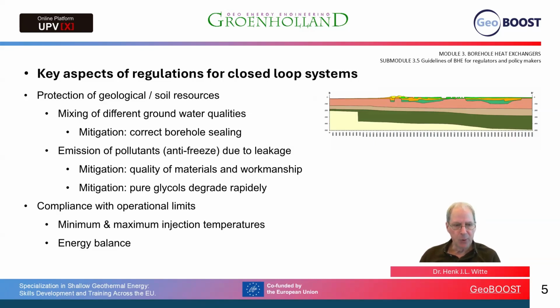Another risk is the emission of pollutants like antifreeze due to leakage in the system. Usually this leakage occurs in the horizontal part. Moreover, if you have the correct quality of antifreeze, it breaks down both biologically and in aerobic and anaerobic circumstances. So actually the effect of some leakages is very small, and very little leakage occurs if you have a good quality of system. So the mitigation here again is the quality of the materials and workmanship, and also the fact that pure glycols like monopropylene glycol or ethylene glycol, or even alcohols like they're used in the north of Europe, biodegrade very rapidly in the ground.